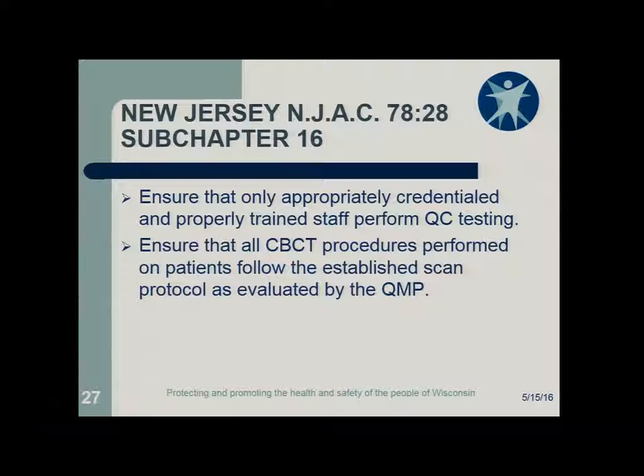Ensure that only appropriately credentialed and properly trained staff perform QC testing. Ensure that all cone beam CT procedures performed on patients follow the established scan protocols as evaluated by the qualified medical physicist. This leads me to another point that Lisa shared with me, and we've been working on too. As you go out to do inspections, when you run across a cone beam CT unit that is newly installed, when they had their applications done, did they willy-nilly do Joe Blow dental assistant to do a test on?